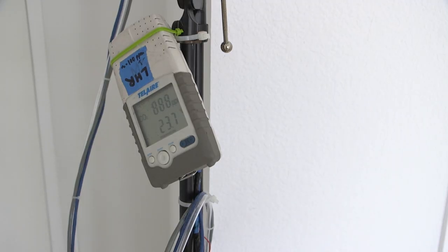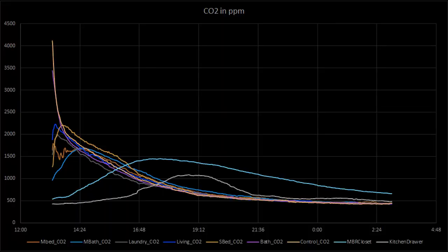There are two kinds of tracer gas tests: decay testing and continuous injection. With decay testing, we have monitors in every room. For carbon dioxide, these are pretty readily available, though you are going to spend thousands of dollars on this kind of equipment. We inject 4,000 parts per million into a room where the air handler is going to pick it up and distribute it around the house. Then when we reach steady state — meaning every room has the same high level of that tracer gas — we shut off the air handler, shut off the HVAC and any fans, and just watch the house drift down. The graph looks like this: you can see that all the rooms reach an equilibrium, then they all start falling off.